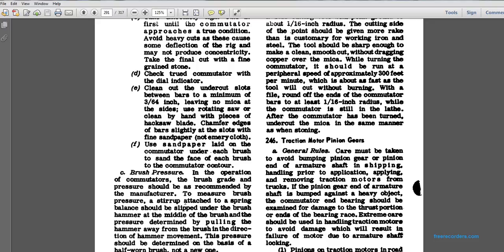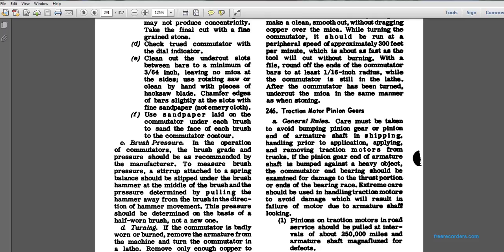Use a sandpaper laid on the commutator under each of the brushes to sand off the face of each of the brushes to the commutator contour. Check brush pressure. If the operation of the commutator, the brush grade and the pressure recommended by the manufacturer, to measure a brush pressure a stirrup attached to the spring of the balance should be slipped under the brush hammer.